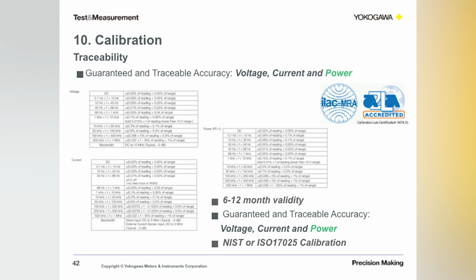The next factor, one of the most important ways to maintain your confidence in your measurements, is to perform regular calibration of your device. Most manufacturers will provide an accuracy validity anywhere from 6 to 12 months. It'll basically have a recommendation that you calibrate this every 6 months or 12 months. But to get good confidence, you've got to calibrate your devices regularly. And the two most common standards for traceability used here in the United States are NIST and ISO 17025. These are both standards that are related.